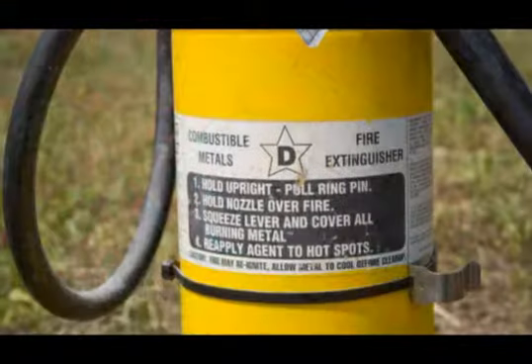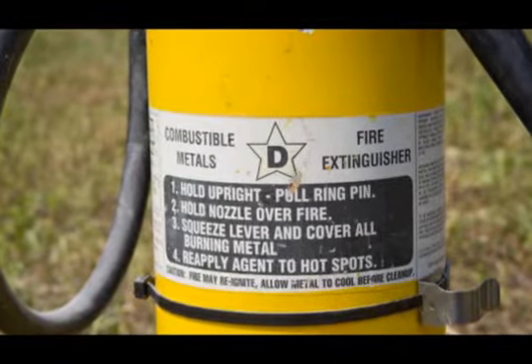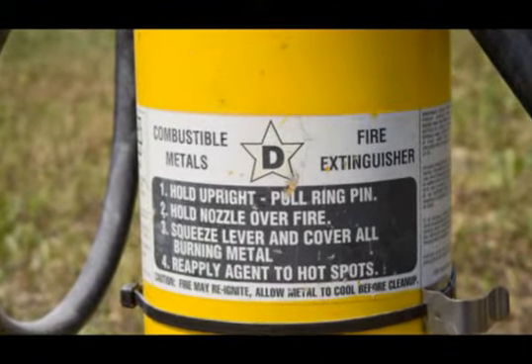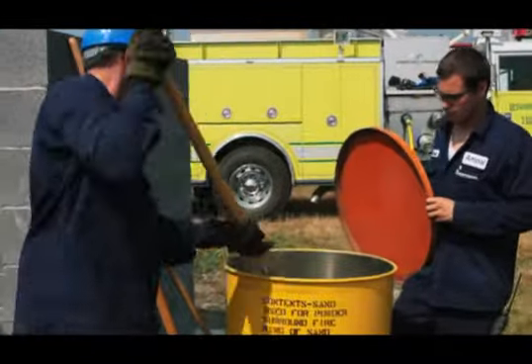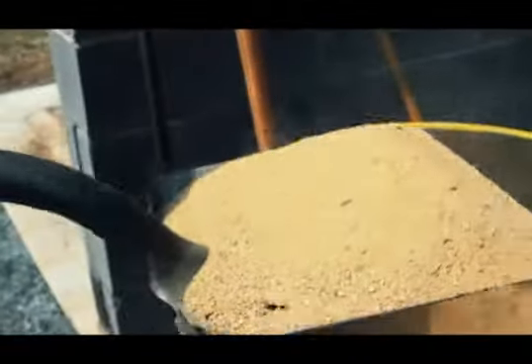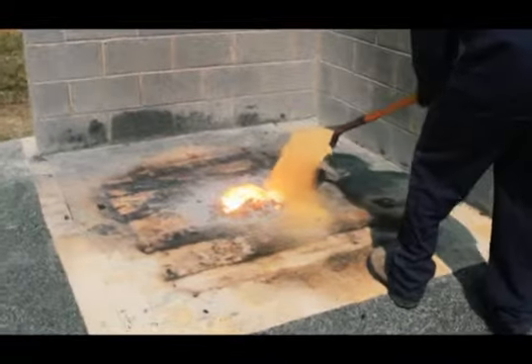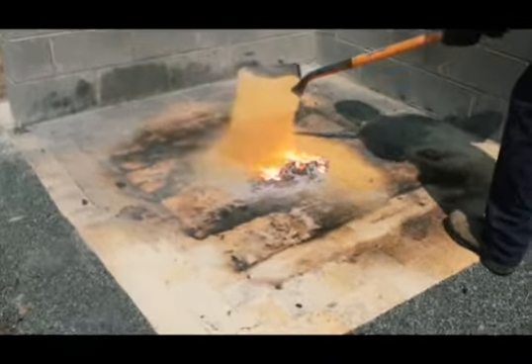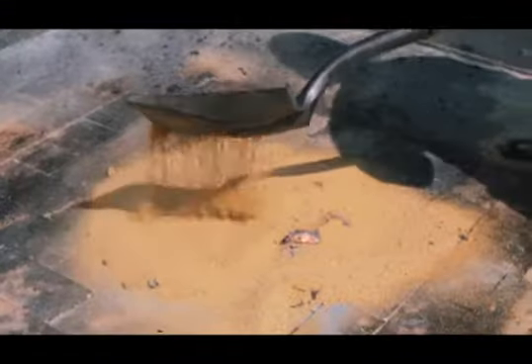Aluminum powder fires on reasonably flat surfaces may be controlled and isolated by blanketing the burning material with a Class D type dry extinguishing agent and then by covering the burning material with dry sand. Long-handled shovels or scoops made of non-sparking material are to be used for the application of dry extinguishing agents. This should be done with great care to avoid disturbing the powder and forming a dust cloud, as even a minor dust cloud may explode violently.